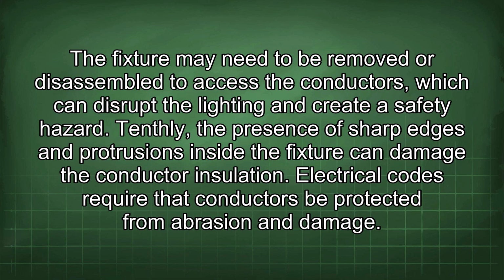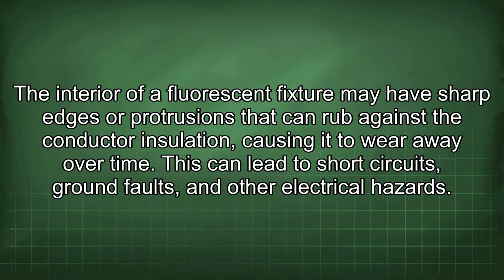a safety hazard. Tenthly, the presence of sharp edges and protrusions inside the fixture can damage the conductor insulation. Electrical codes require that conductors be protected from abrasion and damage. The interior of a fluorescent fixture may have sharp edges or protrusions that can rub against the conductor insulation, causing it to wear away over time. This can lead to short circuits, ground faults, and other electrical hazards.